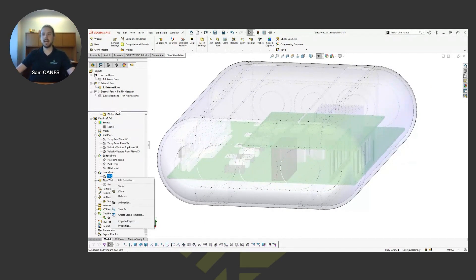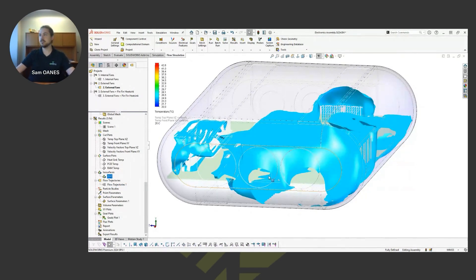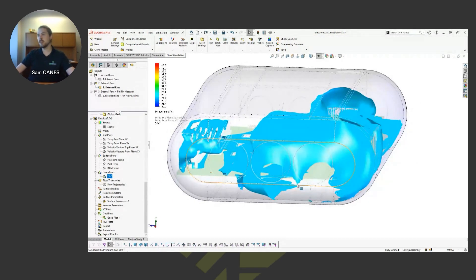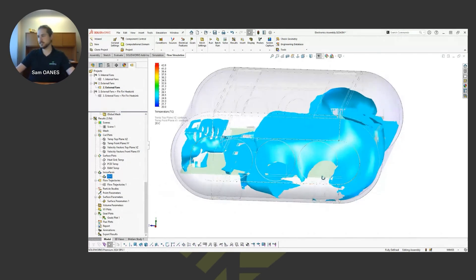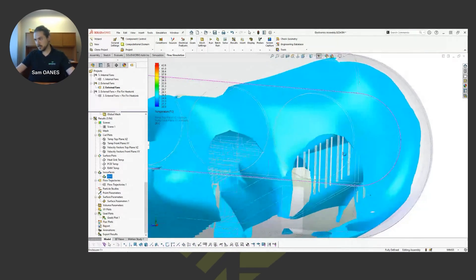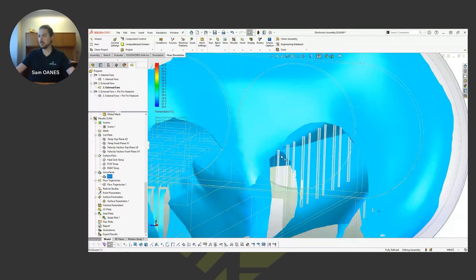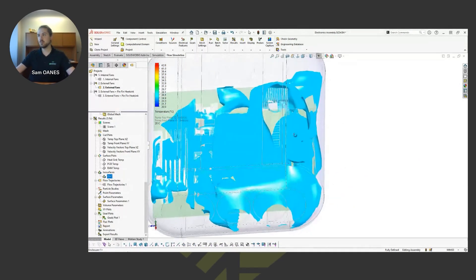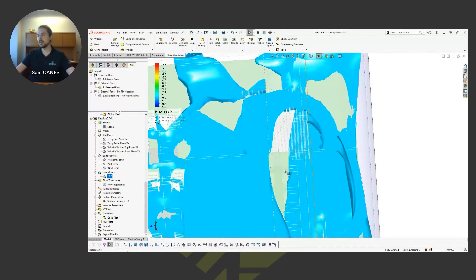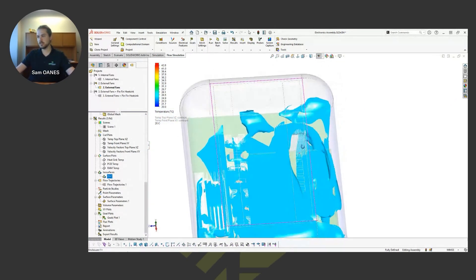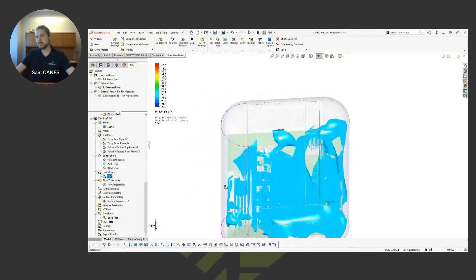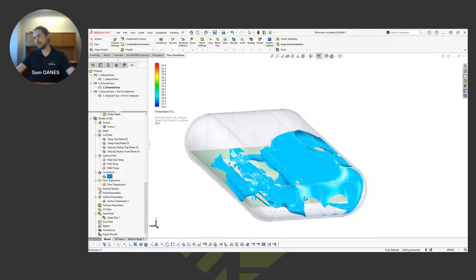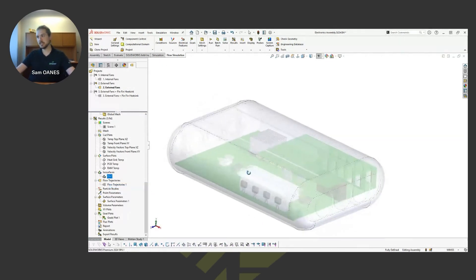A better way to isolate out the information that you're interested in is with this isosurface. What this isosurface does is it's showing us the exact location, an exact profile of where the temperature is exactly 25 degrees C. If that's our target temperature and we don't want it getting too hot around those electric components, 25 degrees C seems like a good place to isolate those. We can see this pocket is getting too hot, and that gives us a bit more of an image of where we're keeping things cool enough. You can see things get too warm on the other side of that heat sink. We saw that local trend already, but we're seeing it another way here with this isosurface, showing where things are doing okay.